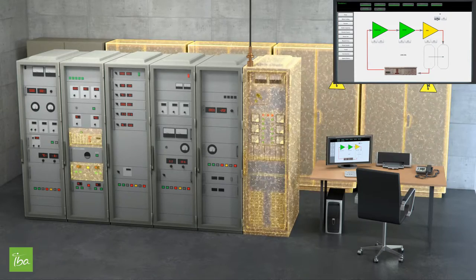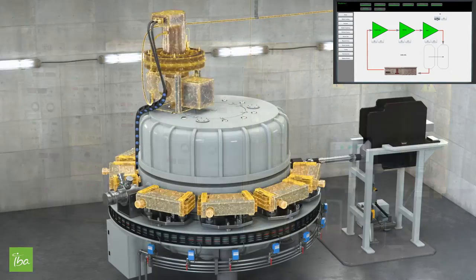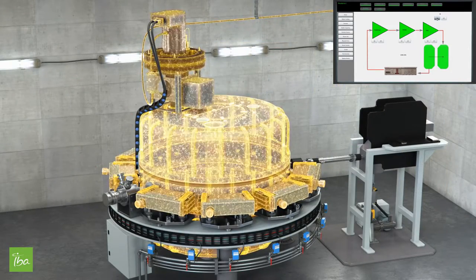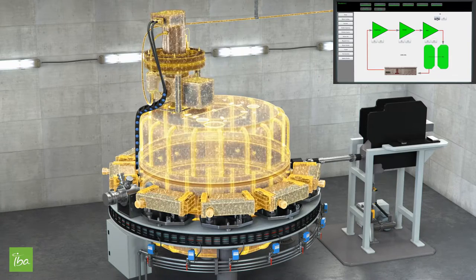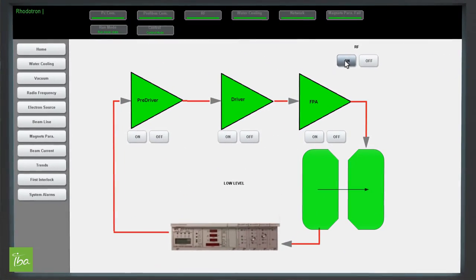And finally, a last time by the final power amplifier located on top of the cavity. This final amplifier is coupled to the cavity to generate the electric field in the machine. Thanks to the modular design of the second generation Rhodotron, this complete RF chain can be doubled or tripled in order to provide a more powerful beam up to 700 kilowatts.